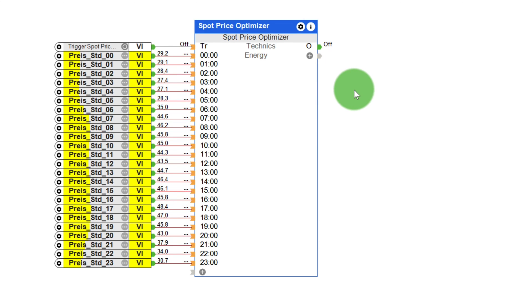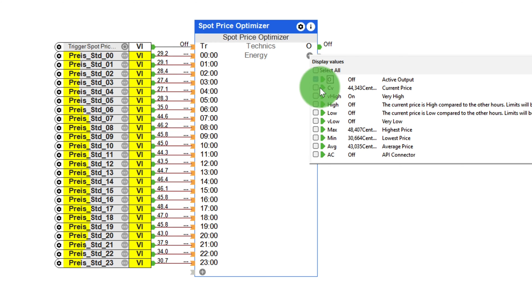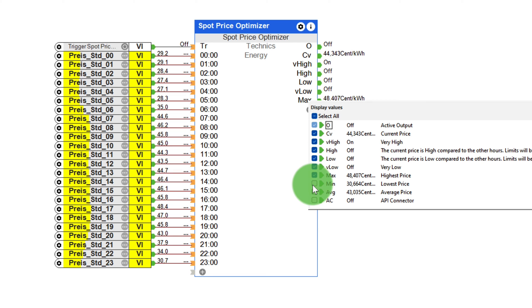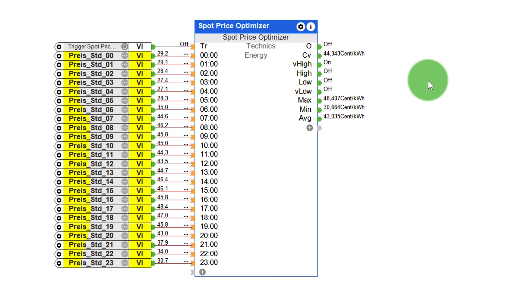Here, we're talking about a cost savings of over 70%. The outputs offer another possibility to take dynamic electricity prices into account with this new function block. These outputs are very high, high, low, and very low. After activating the trigger input, the block determines how the electricity prices develop in the specific period, then activates the four outputs. For instance, if the electricity price is currently very high, load-intensive consumers can be deactivated during this period. In addition, the function block provides additional information, such as the maximum, minimum, and average electricity price. This information can be used, for example, to implement statistics or other individual logic.